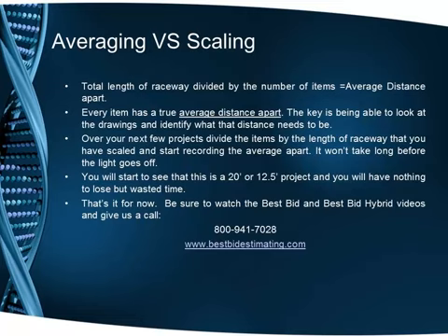Over your next few projects, divide the items by the length of raceway that you have scaled and start recording the average apart. It won't take long before the light goes off. You will start to see that this is a 20-foot or a 12.5-foot project, and you will have nothing to lose but wasted time.